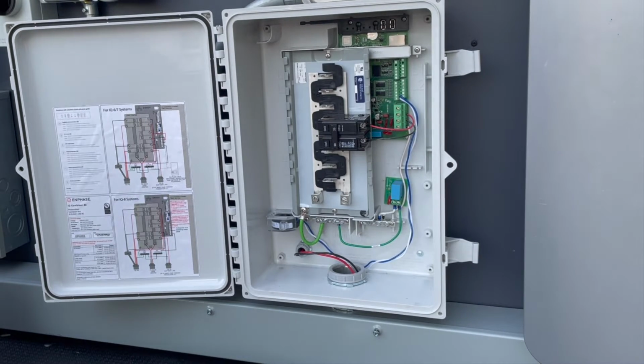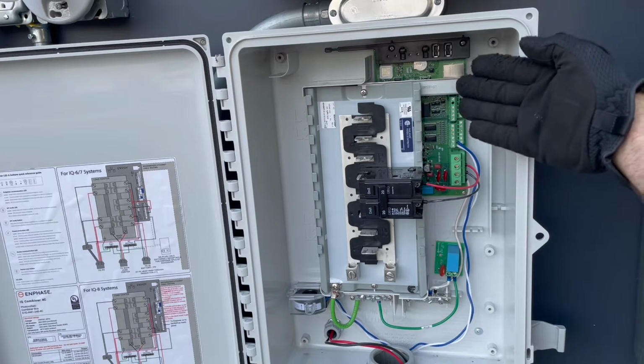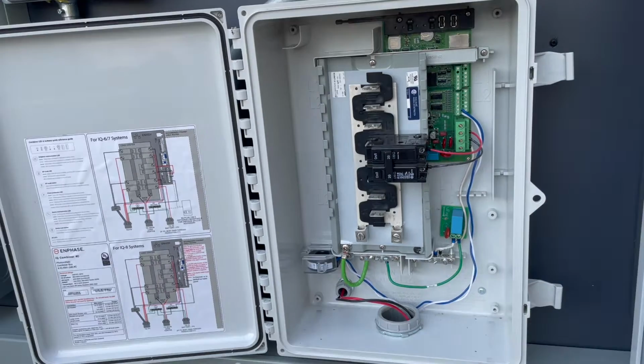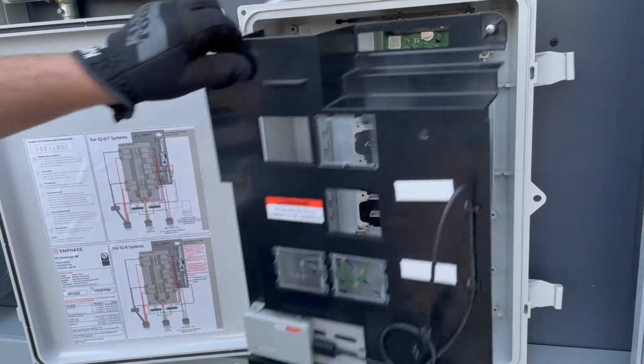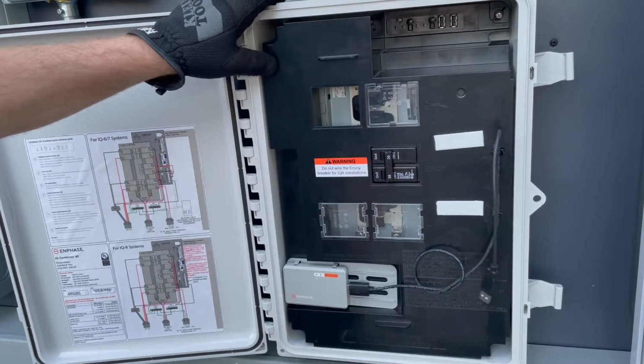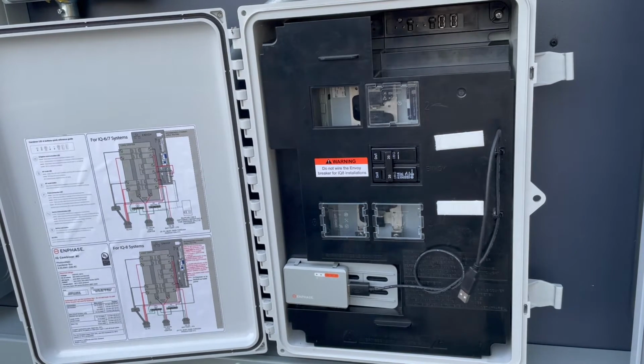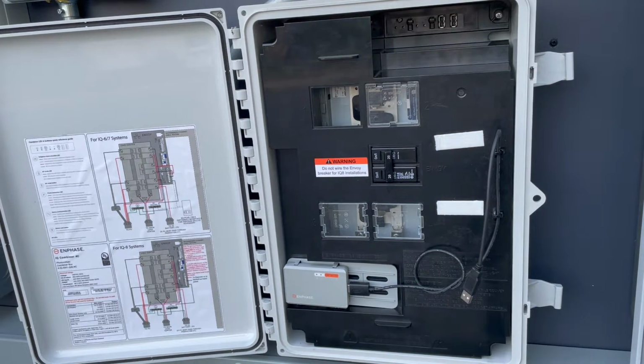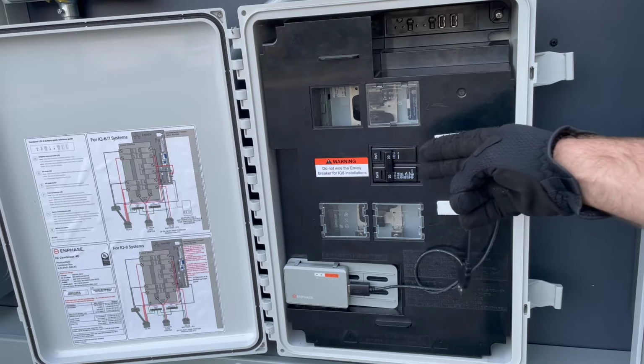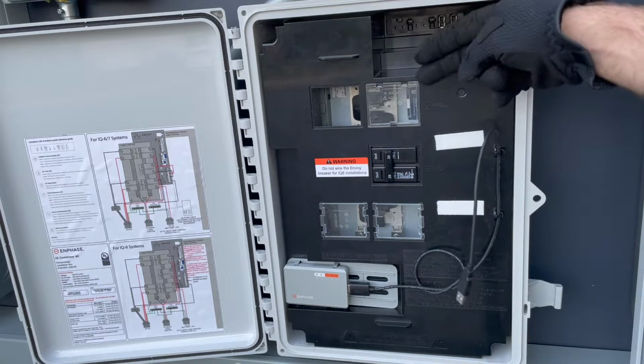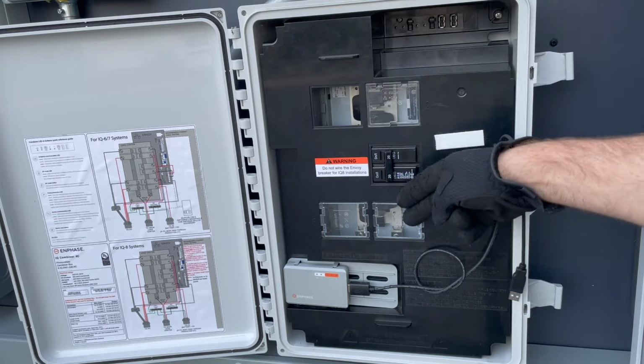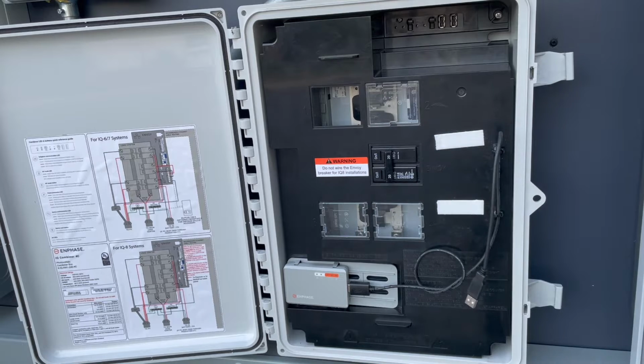Tucked in the back of the IQ Combiner is a compact printed circuit board version of the IQ Gateway. If the site is used in a solar grid-tied only configuration, you can power the IQ Gateway from a breaker located here. The other breaker locations can be used for individual PV AC branch circuits.